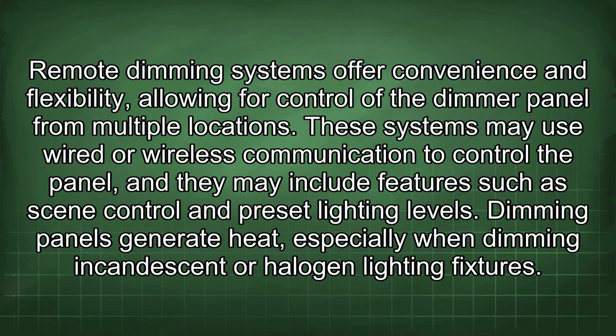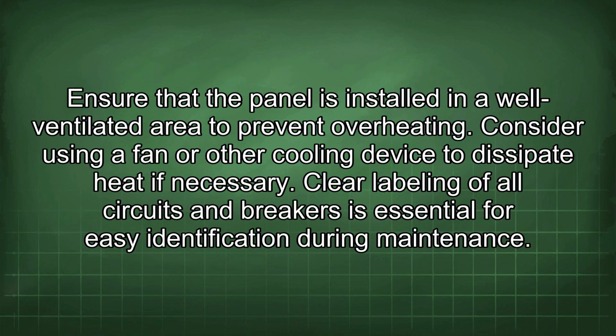Dimming panels generate heat, especially when dimming incandescent or halogen lighting fixtures. Ensure that the panel is installed in a well-ventilated area to prevent overheating. Consider using a fan or other cooling device to dissipate heat if necessary.